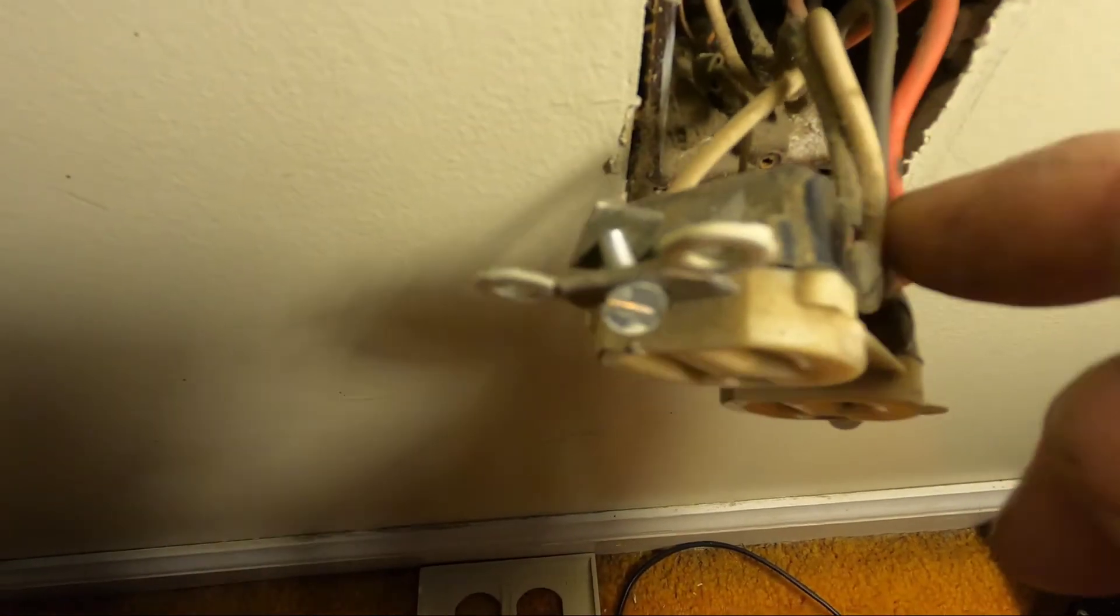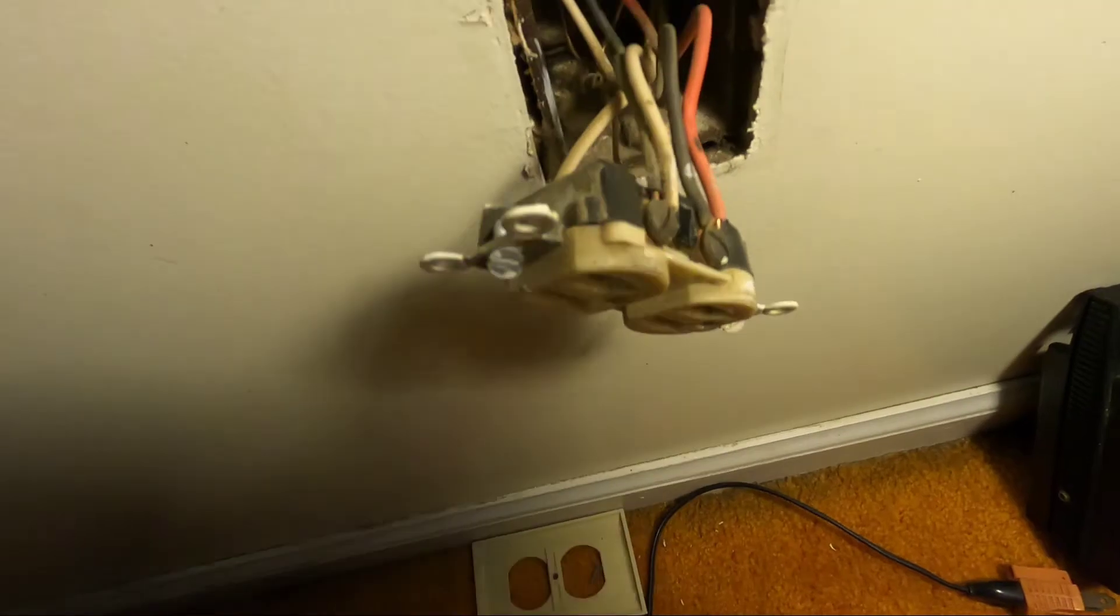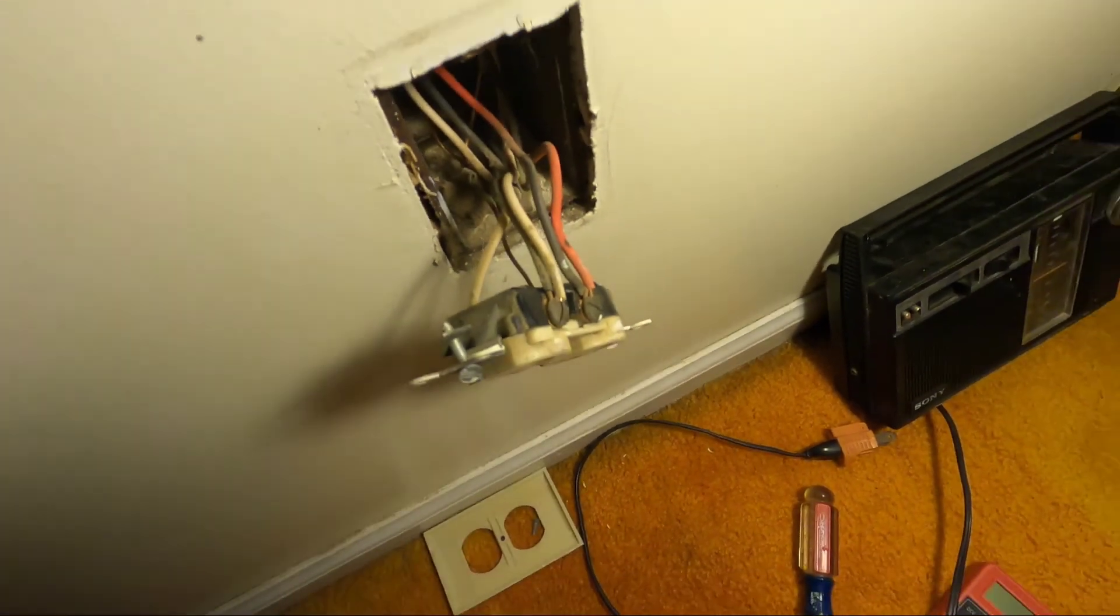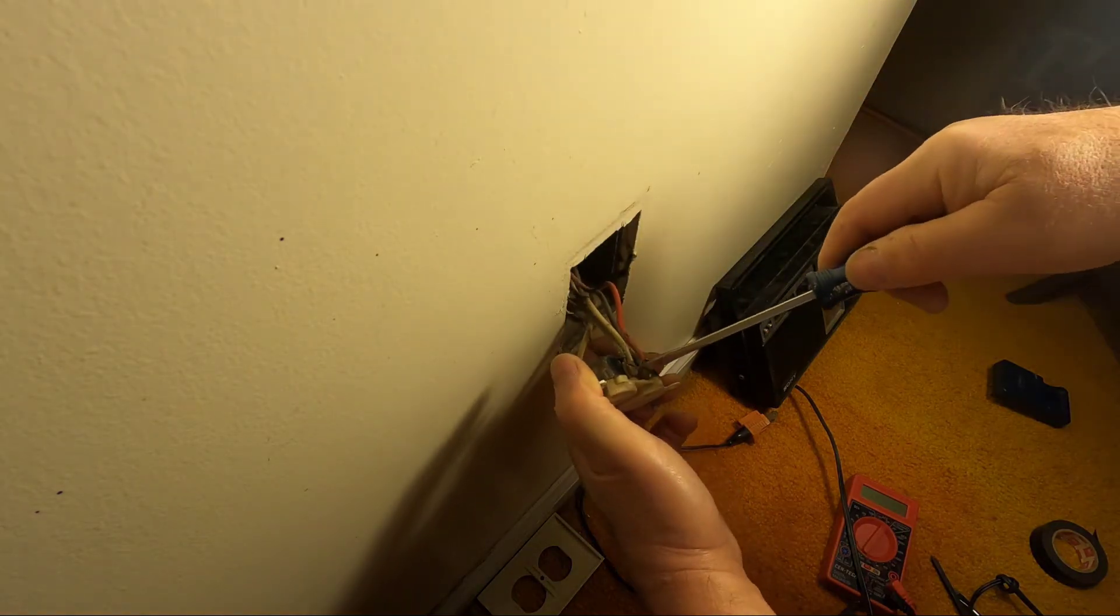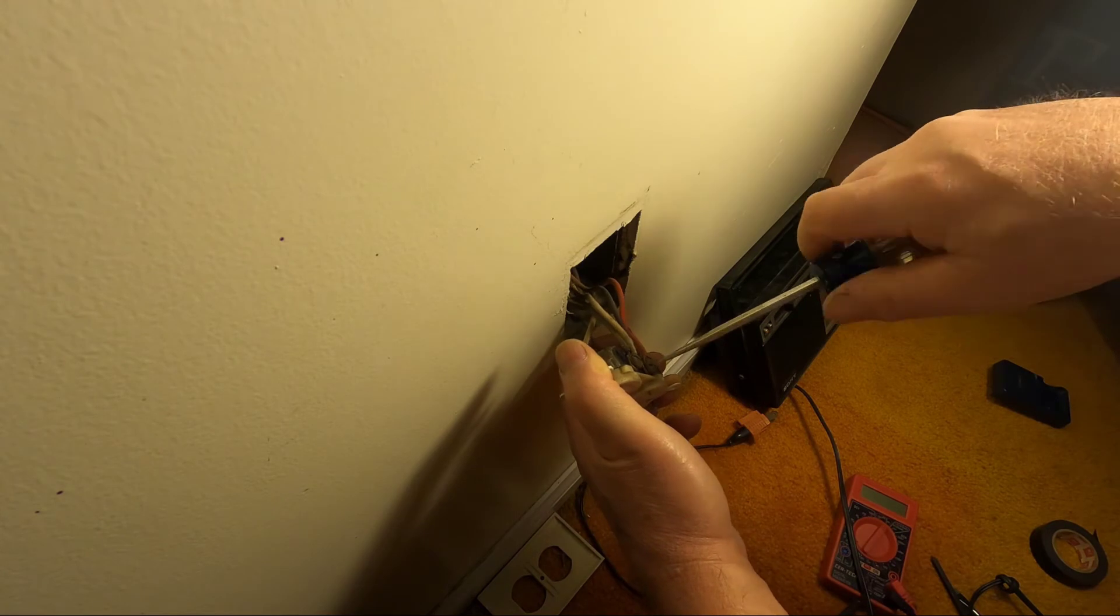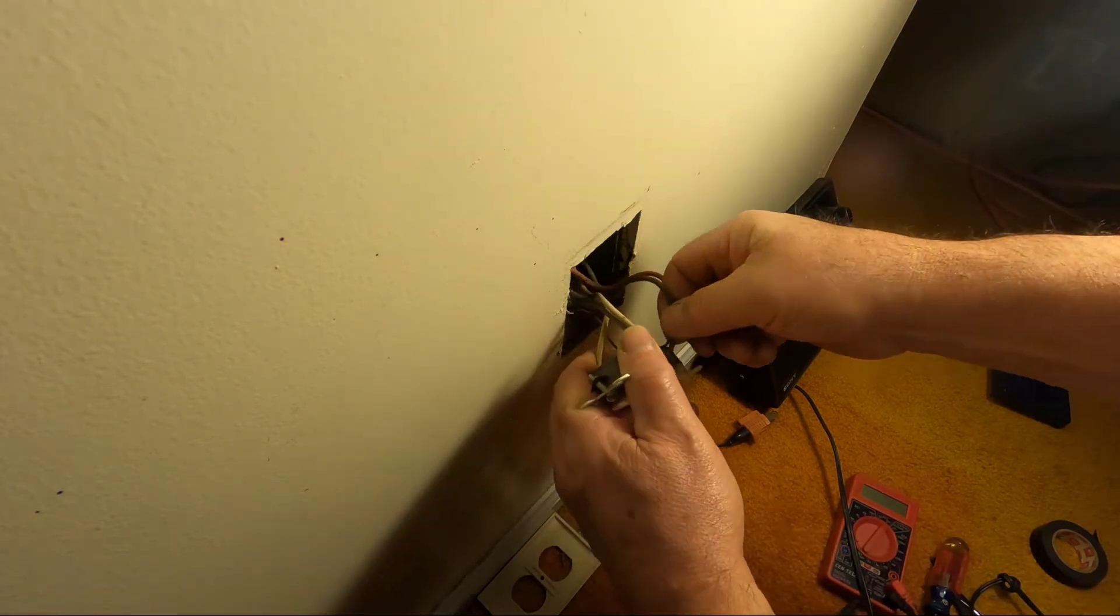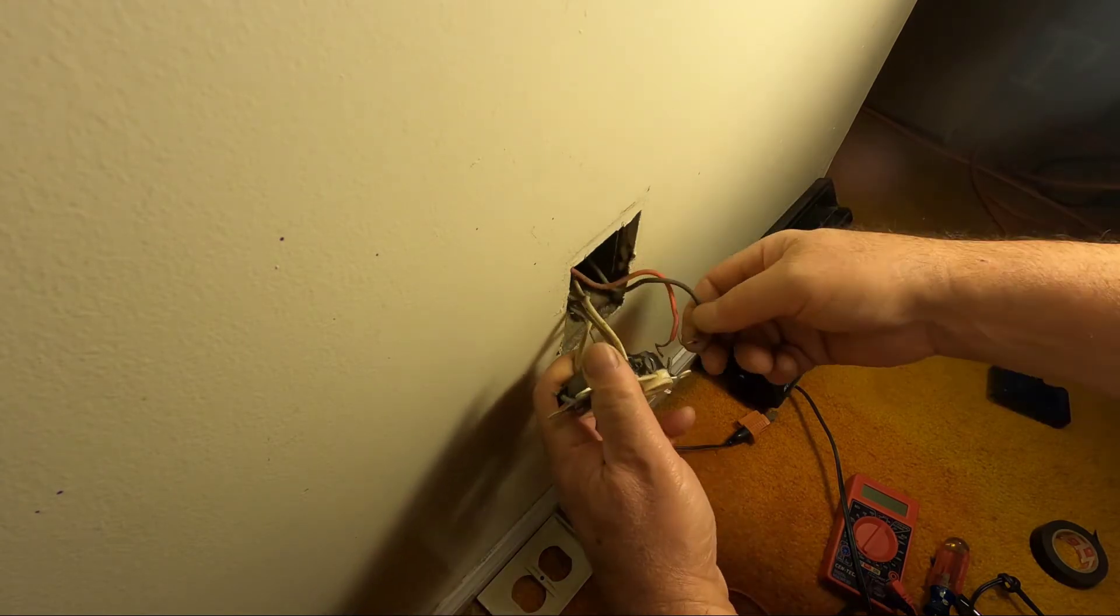Now these wires should be marked. Generally, when you have a white wire that's hot, you put a piece of tape on it, you would paint it, but you can see this wasn't done. So I'm just going to disconnect this right now. There's a little prep when you put a new one on. Sometimes you have to unbend these wires.